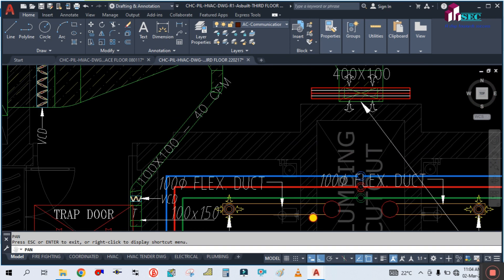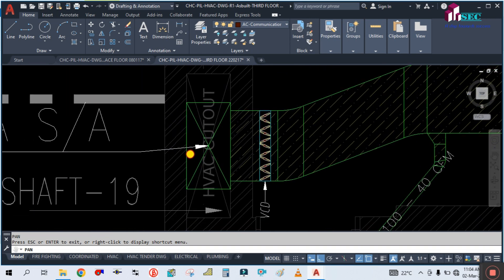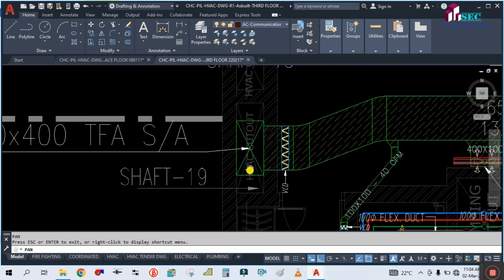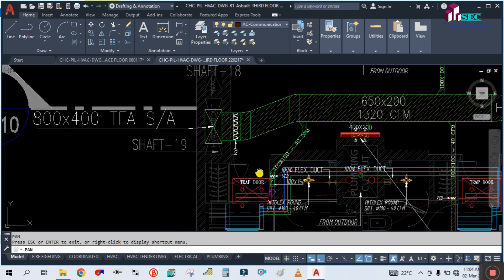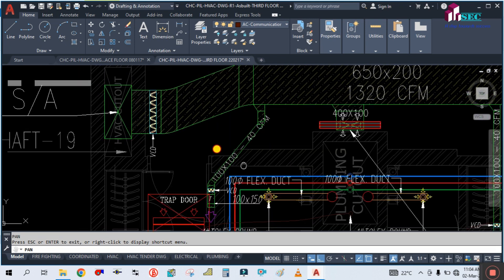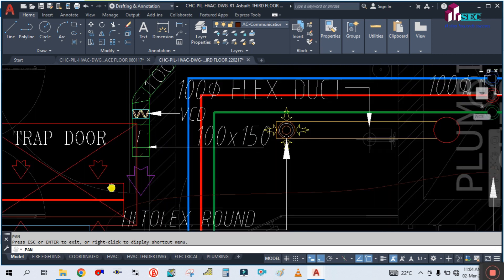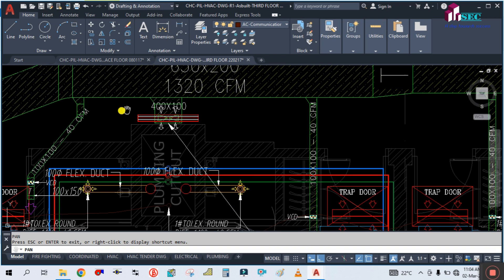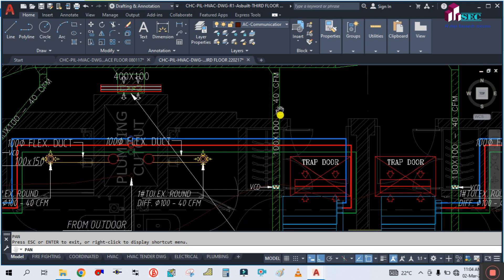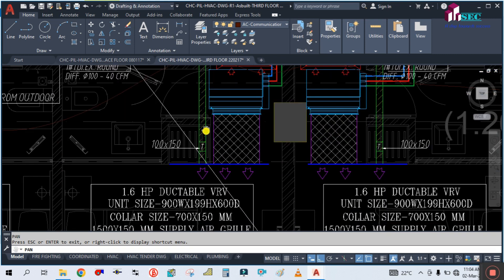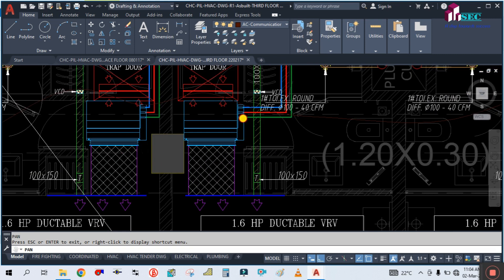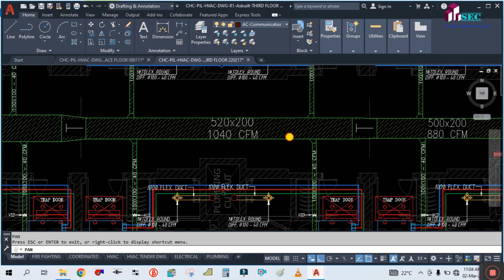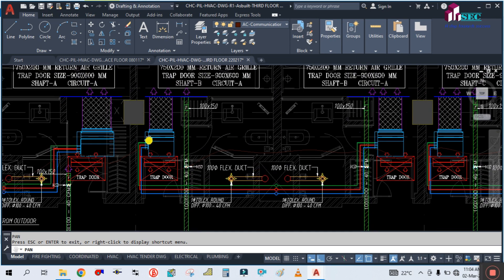The liquid and gas pipe is going into this shaft. This is the treated fresh air — size given is 800 by 400. This is the volume control damper. The fresh air is served near the return of each unit — 40 CFM given to each unit. This is the main fresh air duct serving each room, as each room requires fresh air.